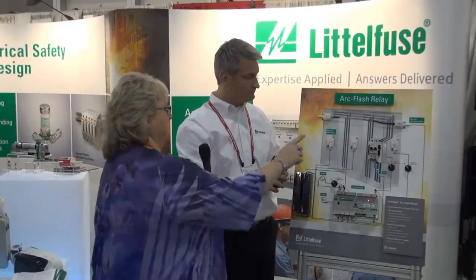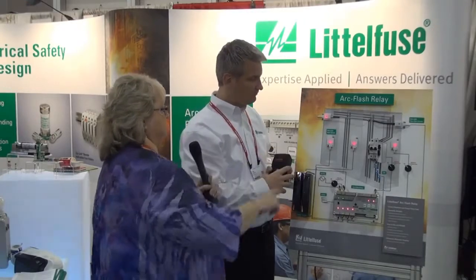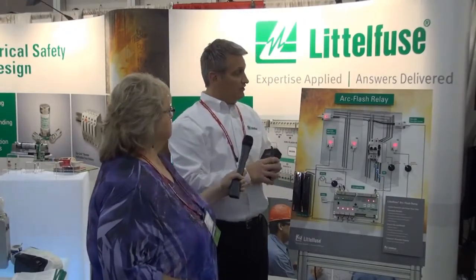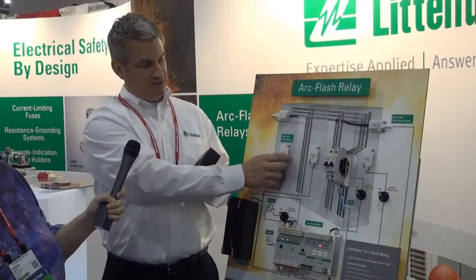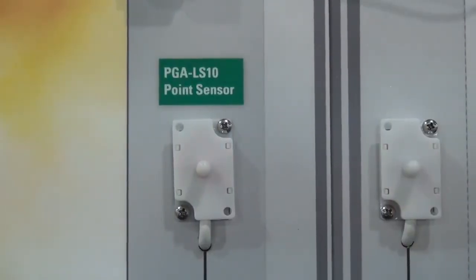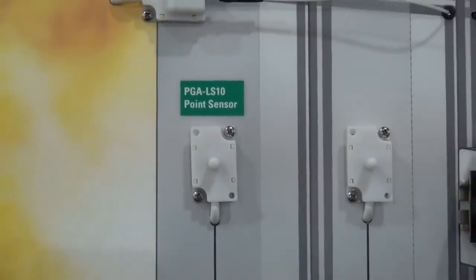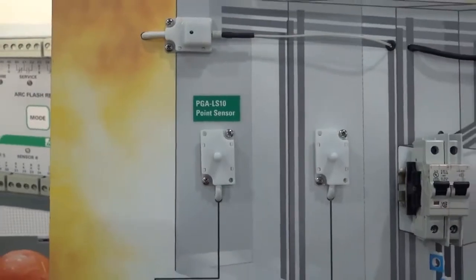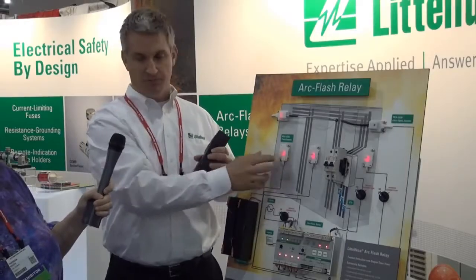Now I see two different kinds of sensors. What's the difference? How would someone choose which sensor to use? So there's two different options. We call this our point sensor. This basically is looking just one direction for about 10 feet out, about 6 feet diameter, sort of a cone shape. This is good for open space. So you may have a transformer compartment, a primary, secondary you can put inside there, or a bigger compartment, a VFD compartment, something like that. That's where these are mostly used.